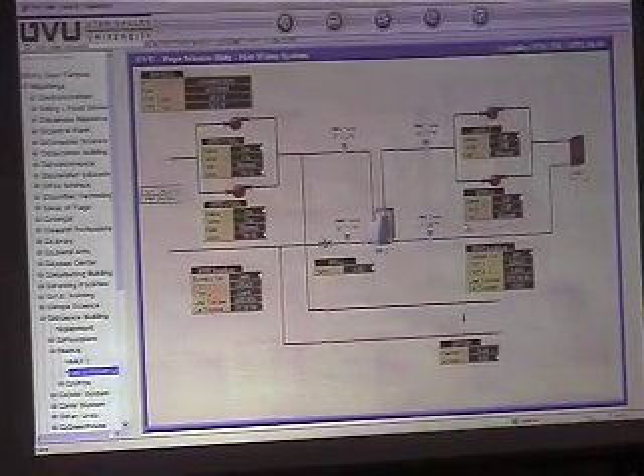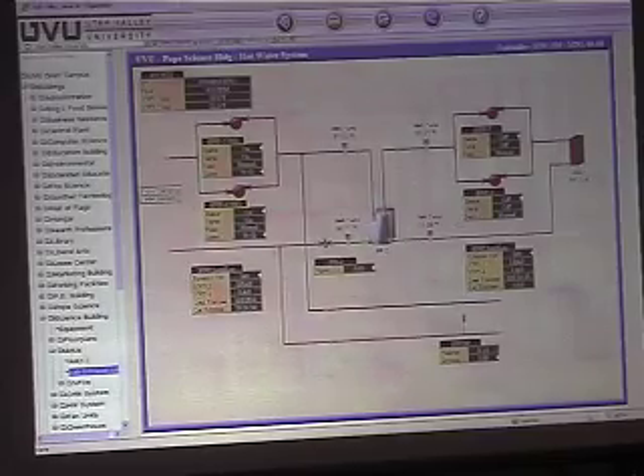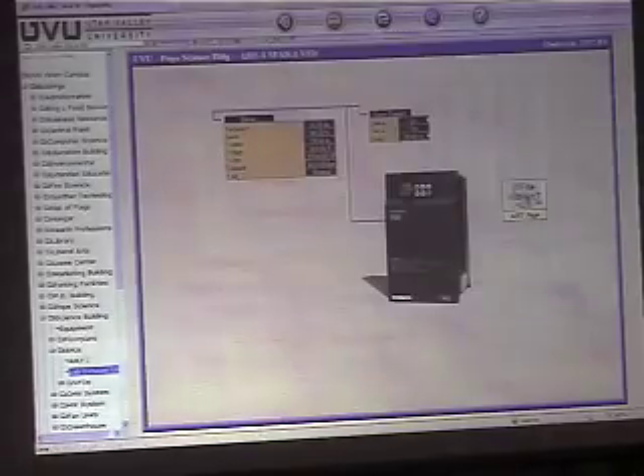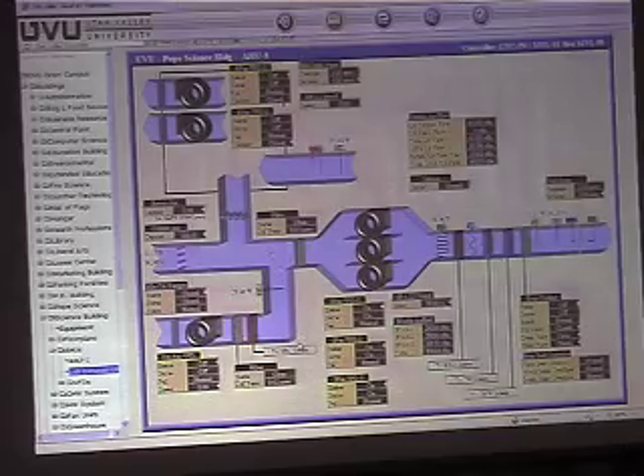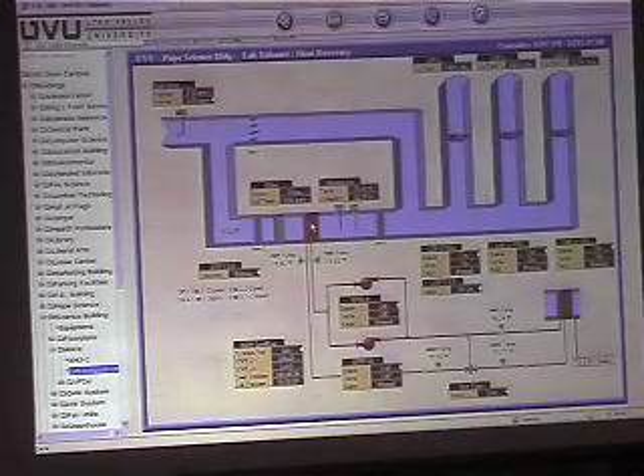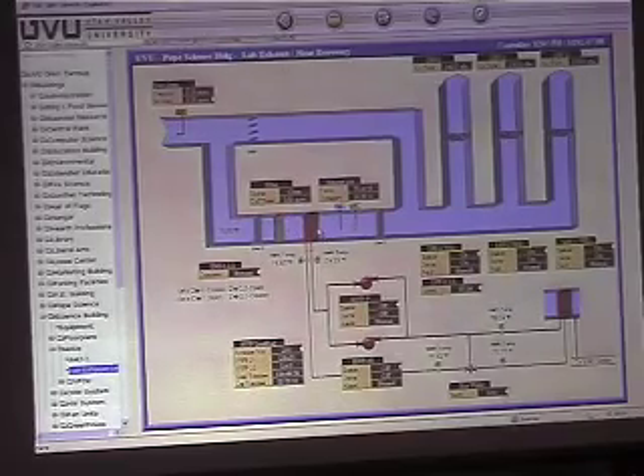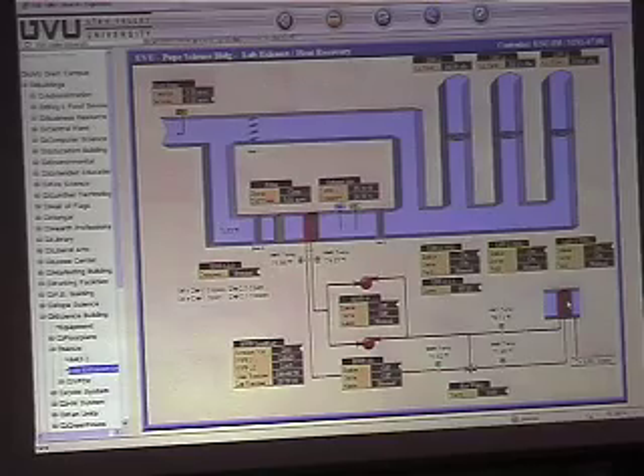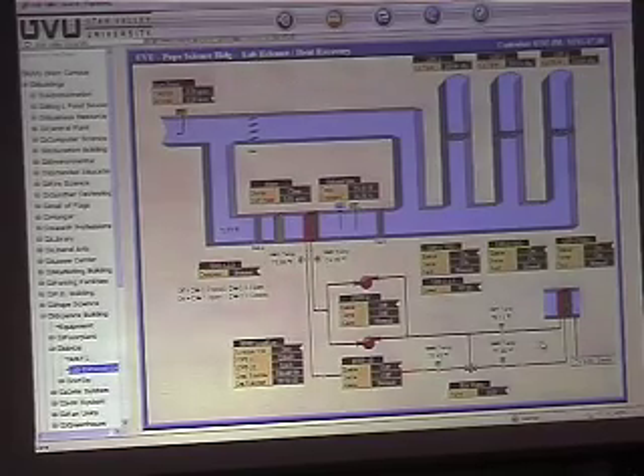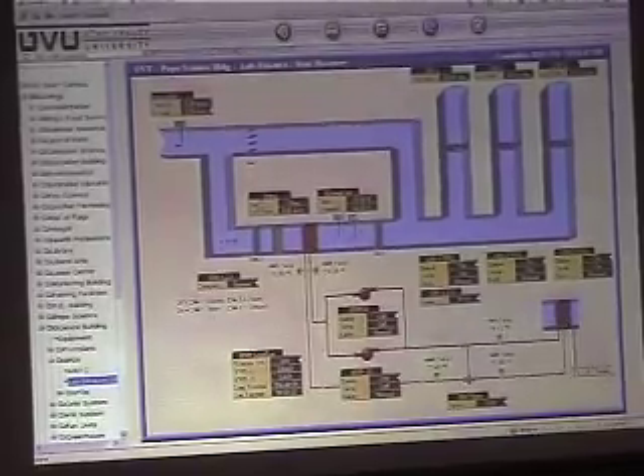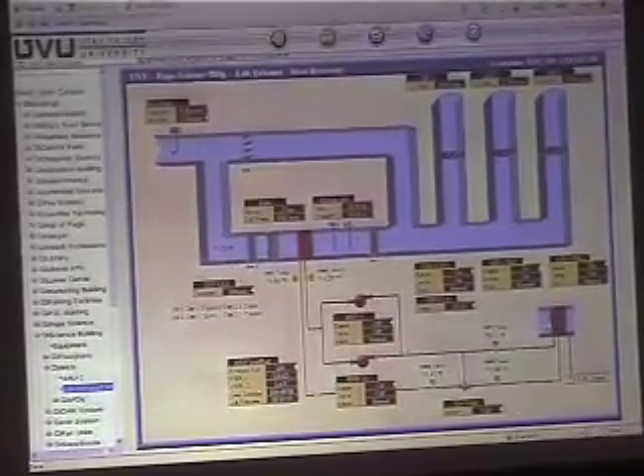The other one picks up heat from the coil in the exhaust and transfers it. That's the only heat source for. Yeah, since you're exhausting air and passing heat through this coil, it just picks that up, these pumps circulate it over and push that heat into here, warm up that water and dump it into here. Is that a closed loop? Uh-huh. It's not tied into anything but just these two right here. Okay. It just circulates between these two coils. Okay.